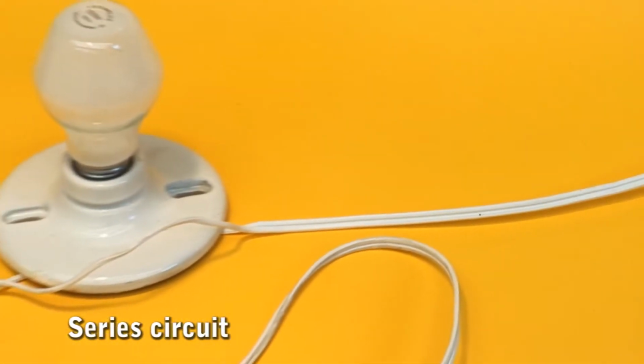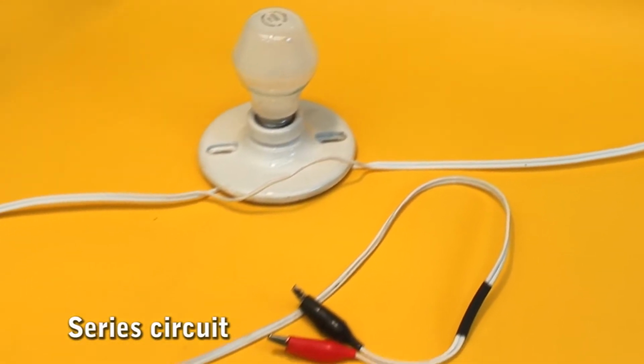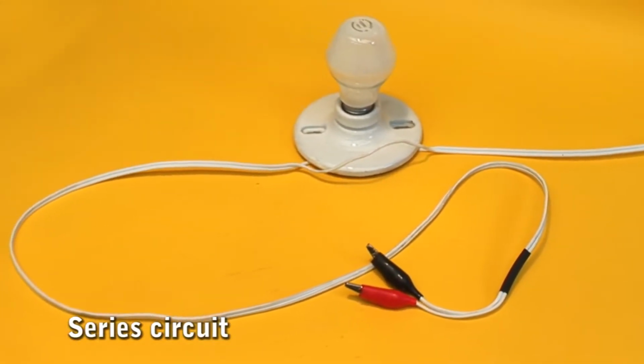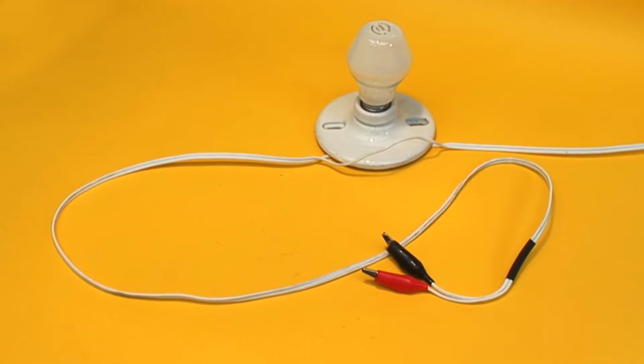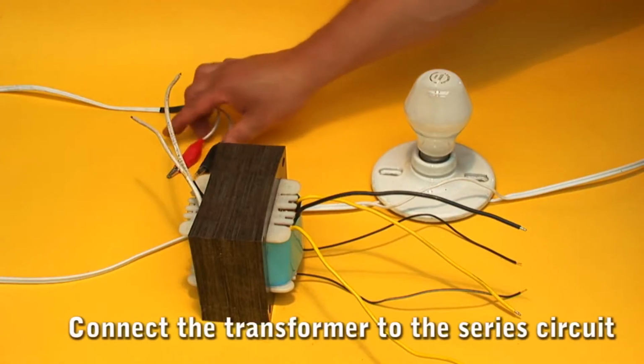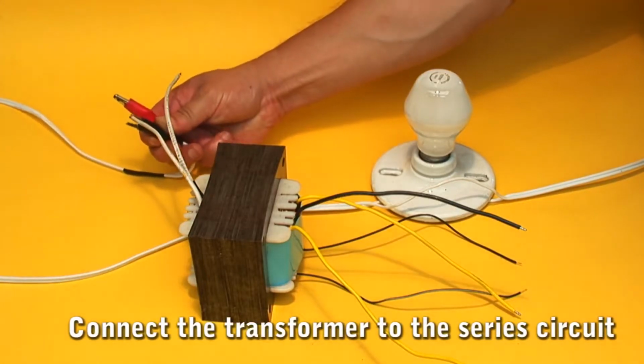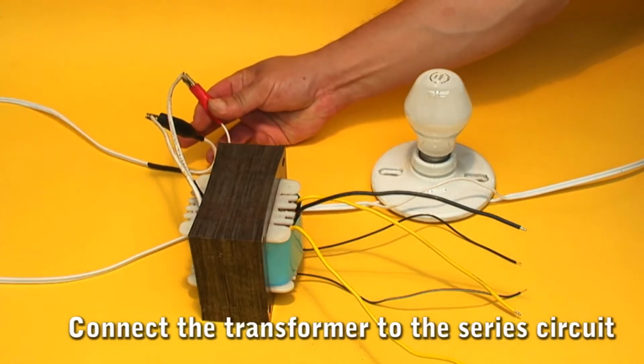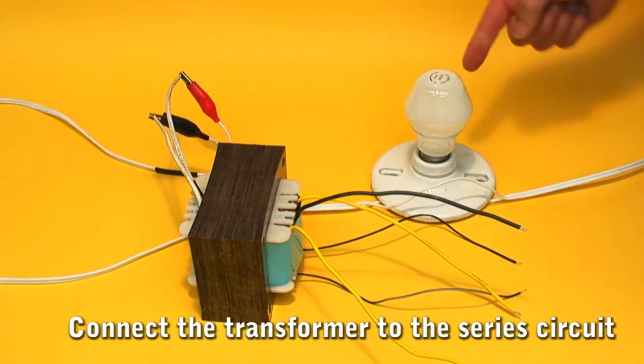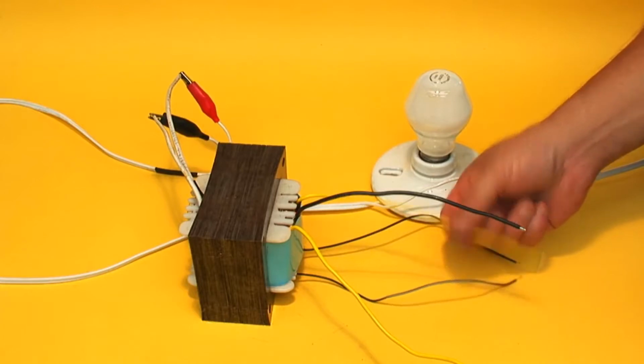Measurements. Series circuit. This system allows testing electric circuits without the risk of burning. If the circuit is shorted, the bulb turns on. If the circuit is not shorted or is open, the bulb does not light. Place the two alligator clips of the series circuit at both ends of the transformer input. The series circuit must not ignite.